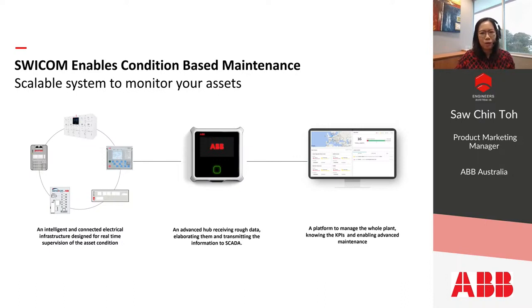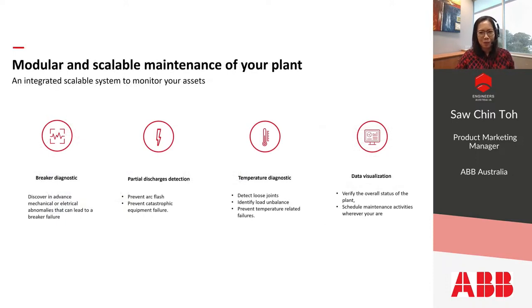Other than SCADA, the SWICOM unit can also be connected to a cloud by subscription to the ABB Ability platform, which Milad, my colleague, is going to talk about after this. This will then enable advanced maintenance using the support from ABB. There are 4 modules included in SWICOM, namely the breaker diagnostic, the partial discharge detection, the temperature diagnostic, and the data visualization module. The first module is the breaker diagnostic module, which will provide advanced warning on mechanical and electrical abnormalities within the circuit breakers.